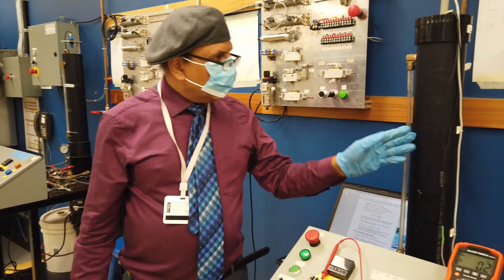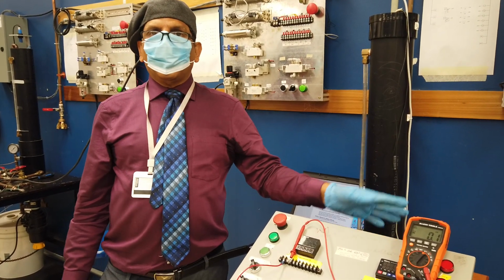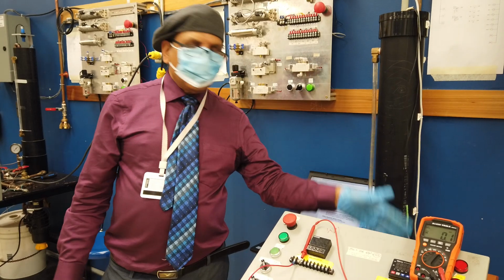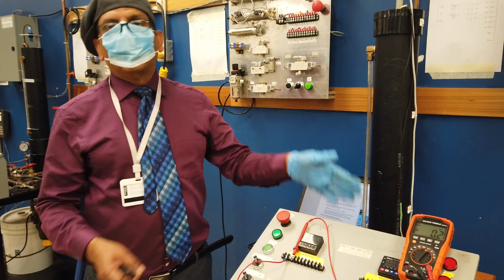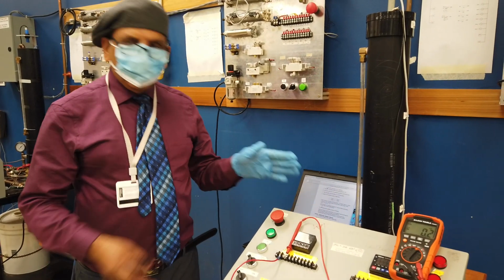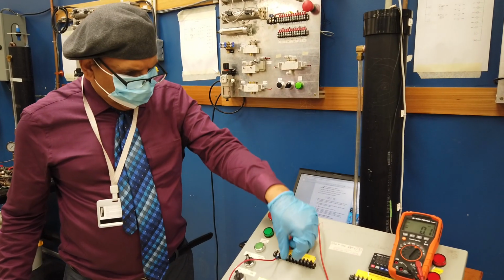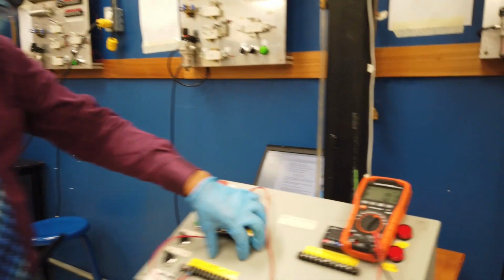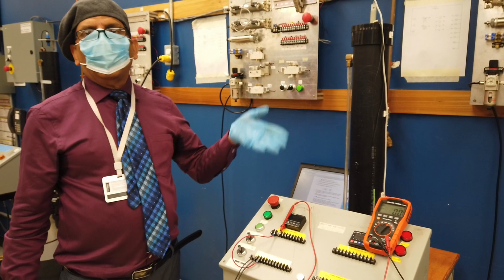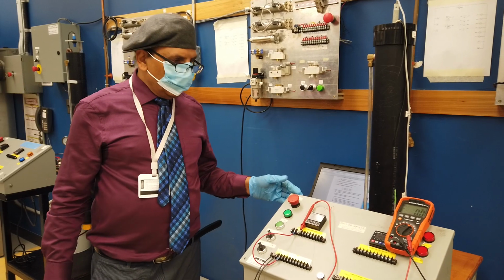And in the process control, in this equipment, we can also do temperature control. We can use the thermocouple as a sensor, and there is the RTD heater. We can use similar programming, but instead of process, we'll put the thermocouple. Okay. We can also measure and control the pressure. At that time, we have to connect the pressure sensor here. Last time we showed the pressure sensor, which is our pressure transducer, and program the same thing. Instead of process, we'll put the pressure, and we can connect it to the controller, and it will maintain. So that's how we can program.